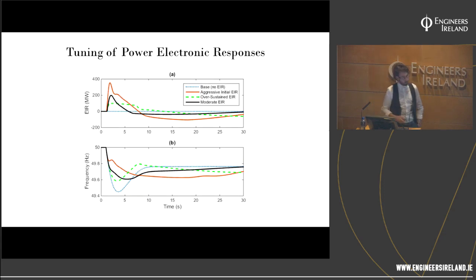If you ask for a longer response, that also will hurt the system frequency, and you can see this decay here. This is roughly 5 seconds, so a governor response is coming up by now. You don't particularly want the wind turbine to continue giving you something there, because other sources are kicking in. You want to give it a high initial injection, but not too aggressive. So you get this moderate, black curve, which I'm going to call a tuned response. Now that's just one case.